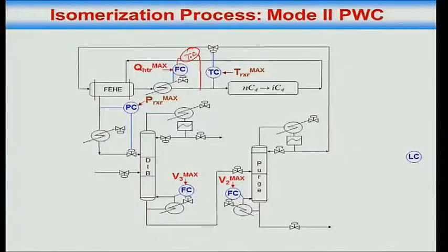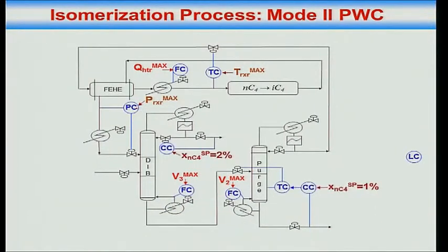Okay, once we agree on that, temperature control is this way. I also need to control the pressure, so I control the pressure by adjusting how much I am withdrawing from here. That gives me pressure control. That's it. Just a second, I also need to control the purities. So I am saying composition control, but this will typically be done using, for example, a delta T measurement.